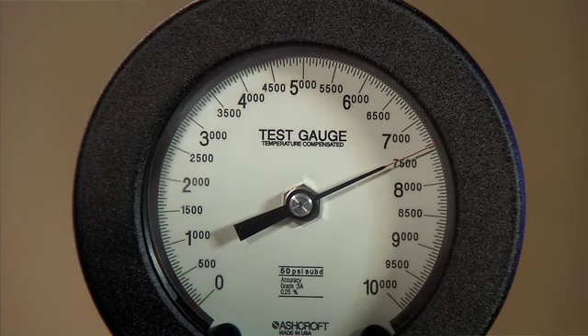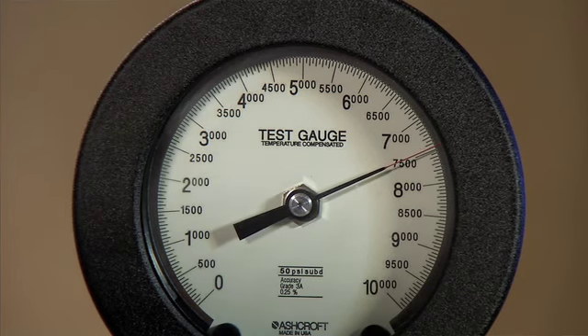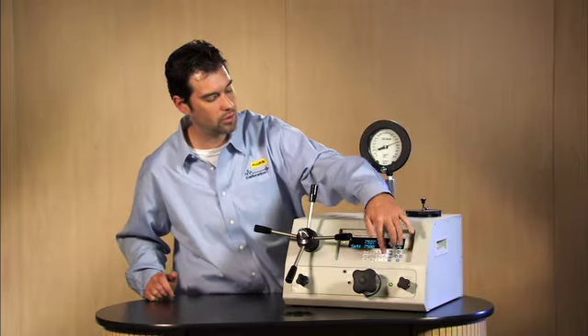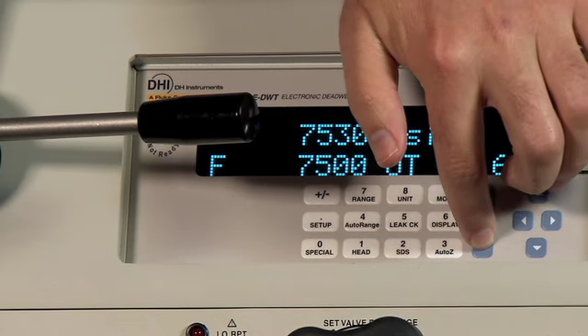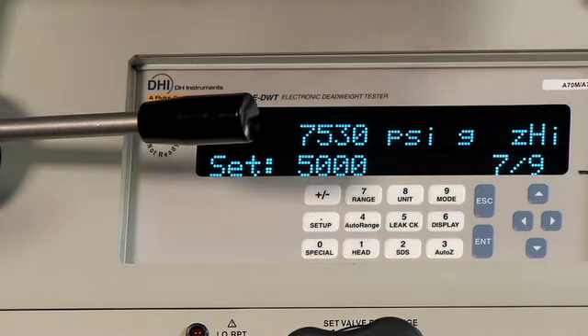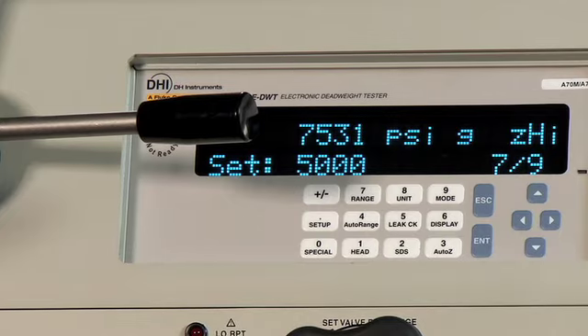I'm at approximately 7,500 psi. Am I ready? Yep. Go ahead and push enter. Still out of tolerance. Acknowledge it. Now we're going to 5,000 psi.